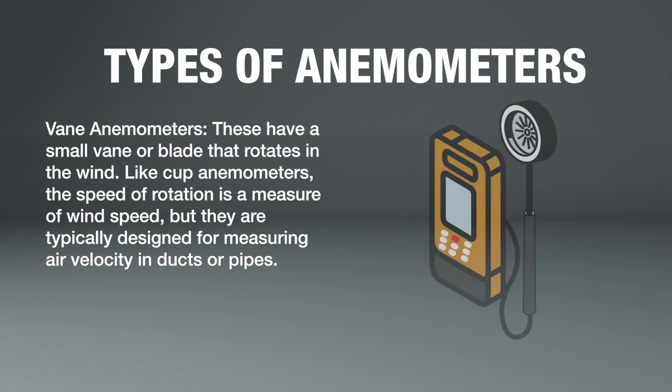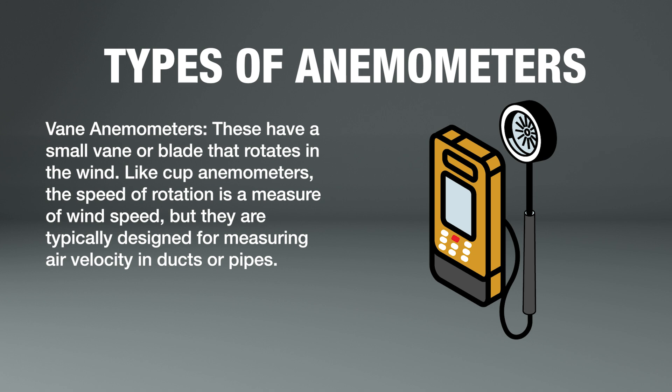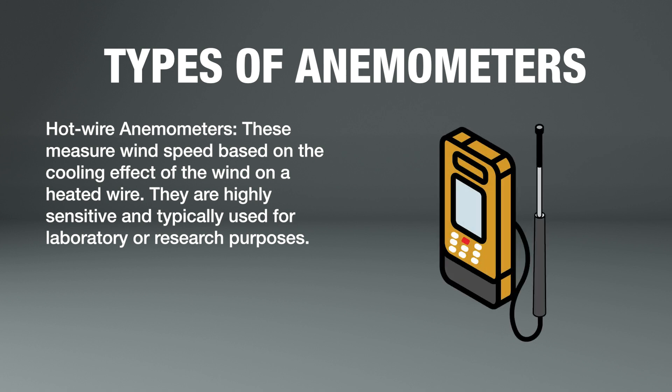Vane anemometers have a small vane or blade that rotates in the wind. Like cup anemometers, the speed of rotation is a measure of wind speed, but they are typically designed for measuring air velocity in ducts or pipes. Hotwire anemometers measure wind speed based on the cooling effect of the wind on a heated wire. They are highly sensitive and typically used for laboratory or research purposes.